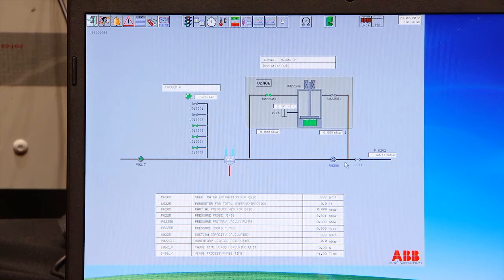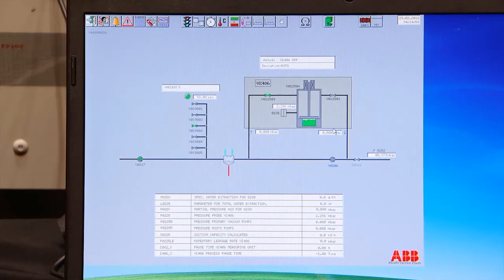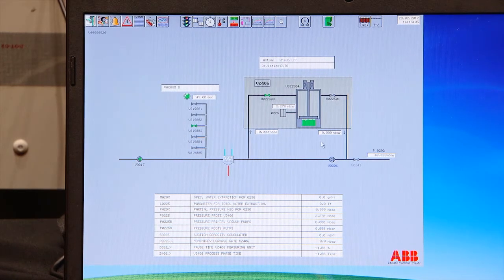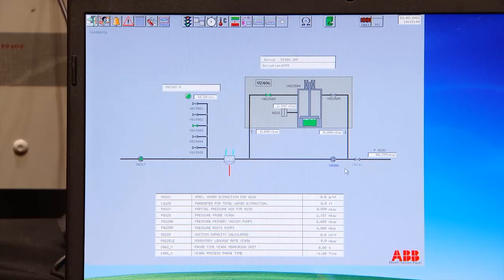I thought you were just talking about when it's doing the reading. Yes, when the 406 is doing its reading, the end pressure will be affected by the vacuum pump capacity, which we are measuring now, and it will be affected by how much water content is in the vacuum coming out. That's the whole idea. We are making those 2 differences. I would take a reading for each degasifier.